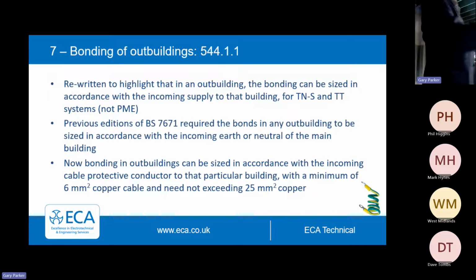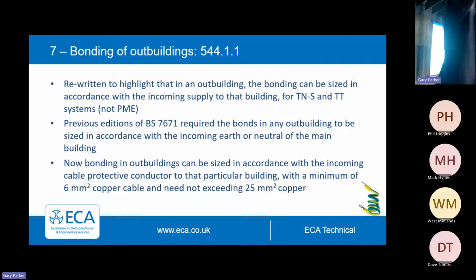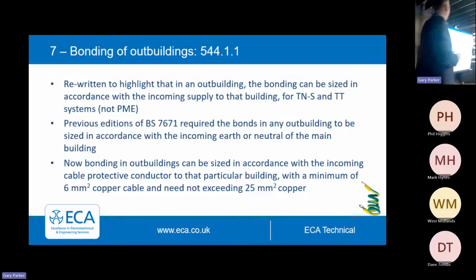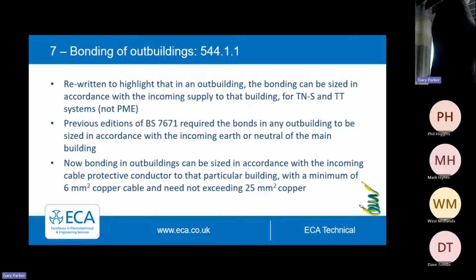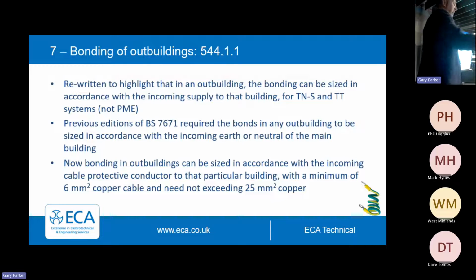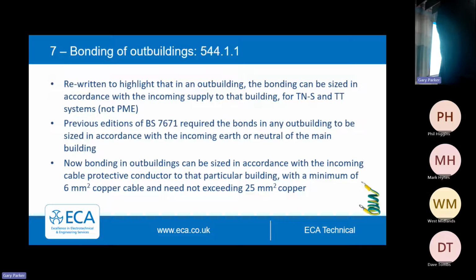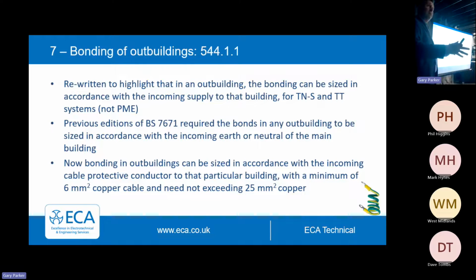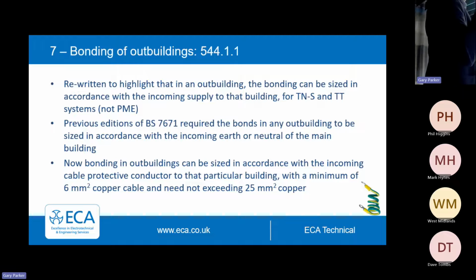So if you were doing not a student accommodation, but a building like this, where you've got multiple outbuildings fed from here, if it was a TNCS PME system, the bonding requirements have to mirror what's in here. You have to mimic the same size. So the easy example is my house. I've got a little wooden shed in my back garden. My house is on PME, I have 10mm bonding, brilliant. If I take a supply out to my shed, I can do that in a bit of 1.5, 2.5, fine. If I put something in there that needs bonding, I've suddenly got to run a blooming big cable, I've got to use a 10mm cable because that's the same size as what's in the mains.